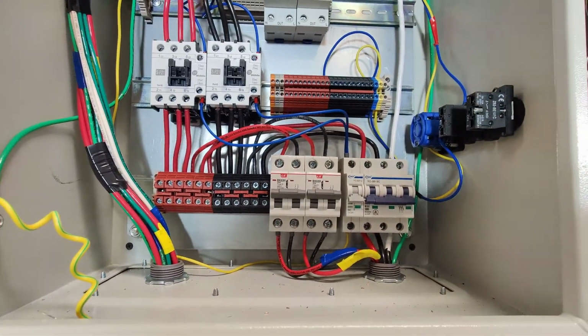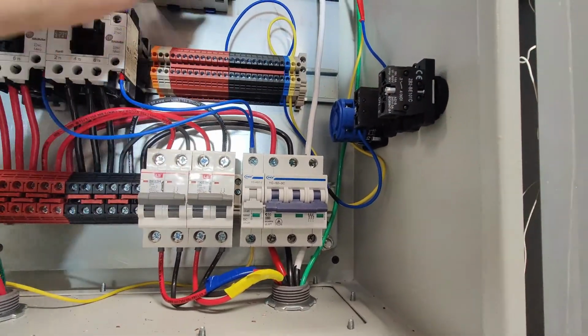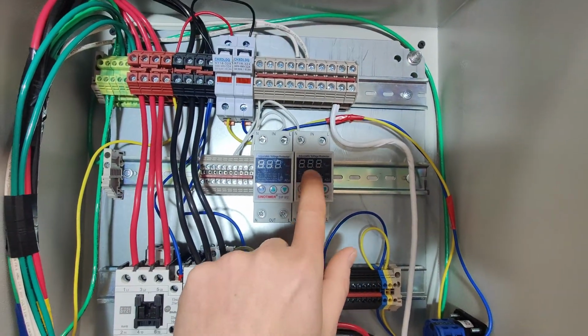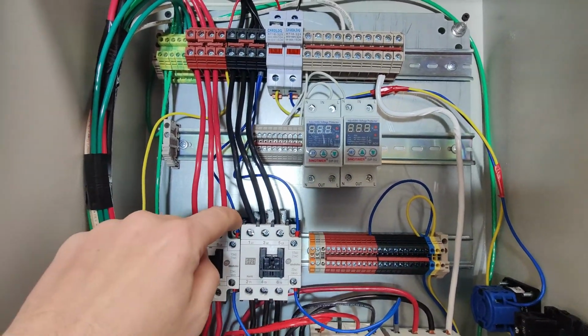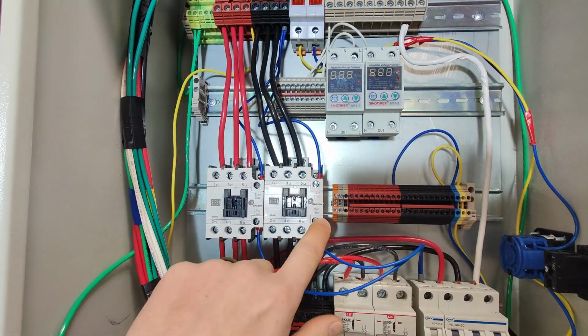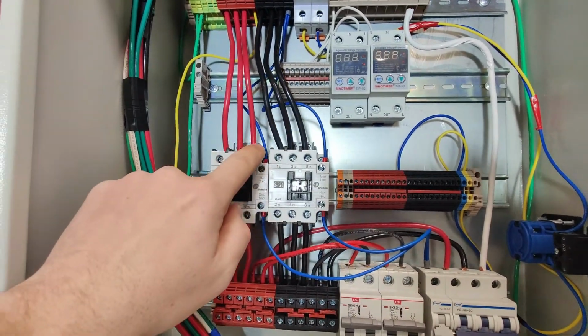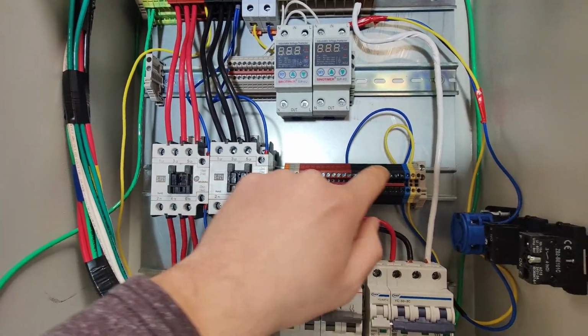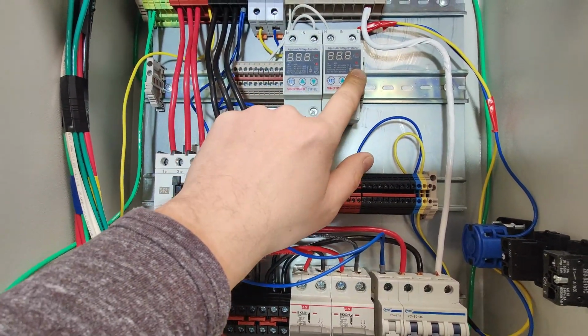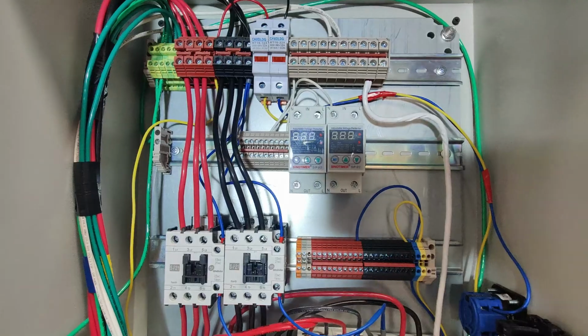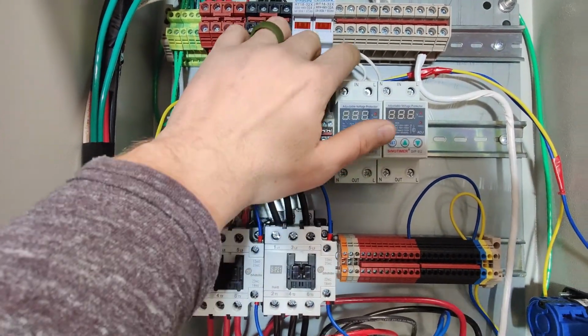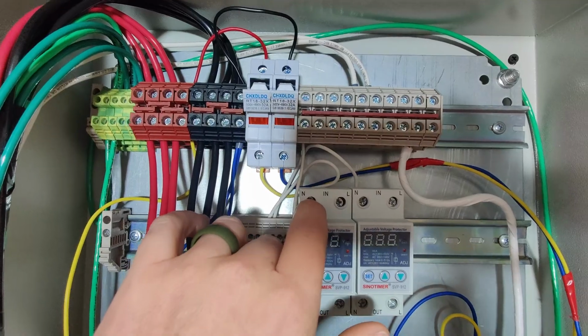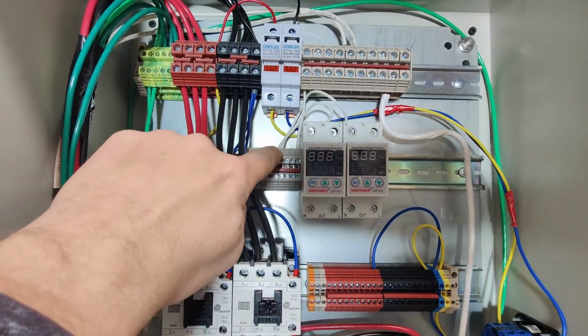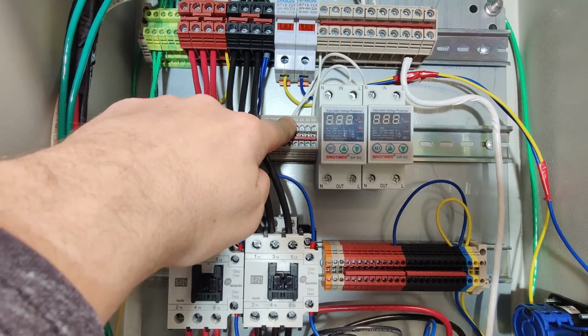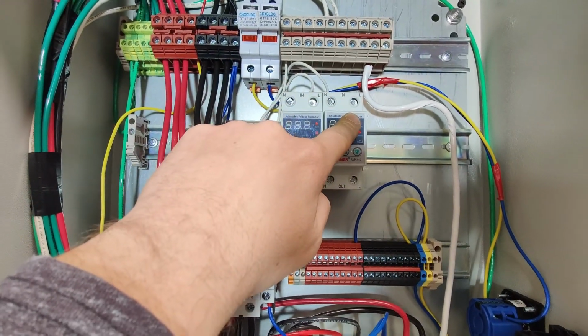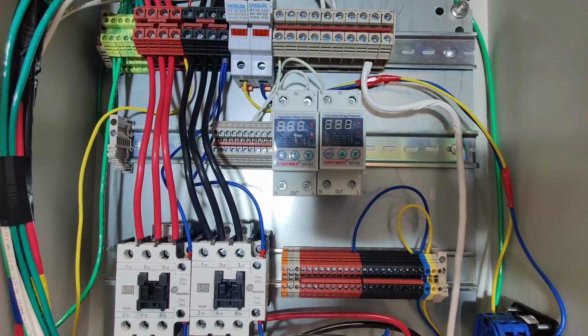Cool. So let's go on to the next steps. What we're going to do is wire up the voltage protector side of this circuit, and we're going to be using the normally open side of the contactors. We're going to come power out of here into the normally open, and we're going to do this for each hot leg because each voltage protection relay is monitoring an individual hot leg. You can see that I've already got the neutral side wired in, and that neutral side is just coming directly off of our bus bar here down to this bus bar here and this bus bar here. That's just passing the neutral directly in. So we'll go ahead and get that wired up.